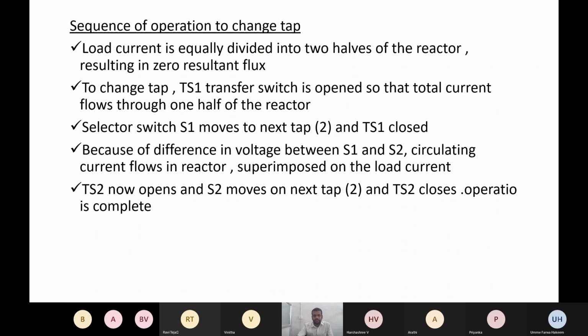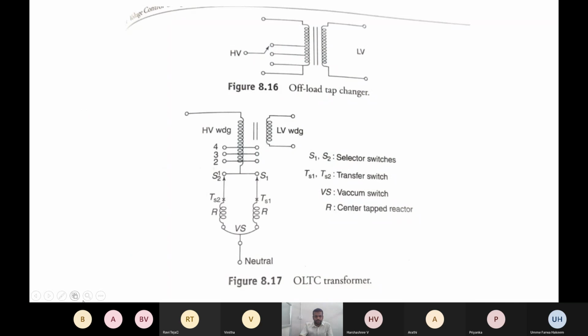So what are the different kinds of switches there? These are our selector switches, S1 and S2. Based upon the maximum voltage, we are keeping the voltage at the maximum in the HV winding. The selector switches are selected by the physical tap position on the transformer winding, and these are not used to make or break any load current. Making or breaking of load current will be done by the circuit breakers, that is, by other switches. The selector switches only select the tappings of the winding. That is by physical nature.